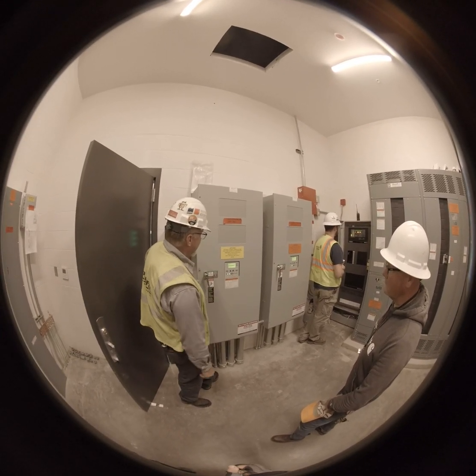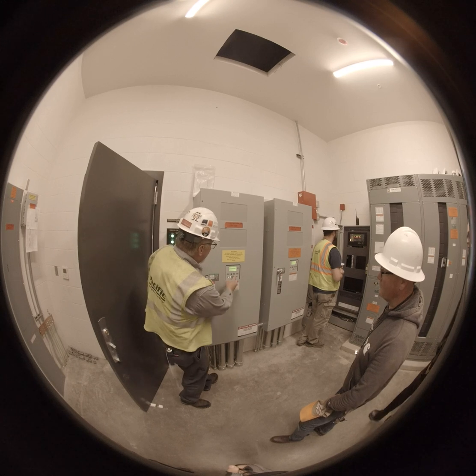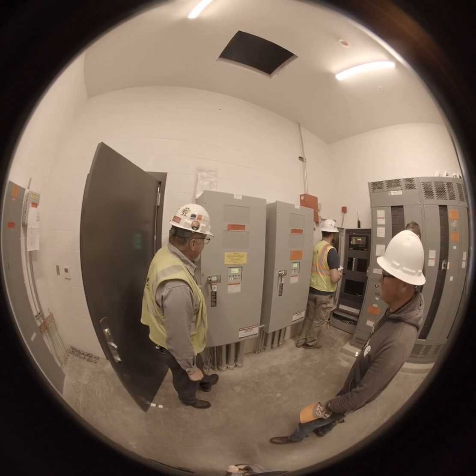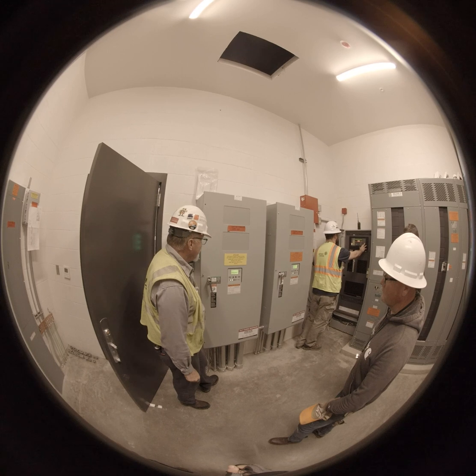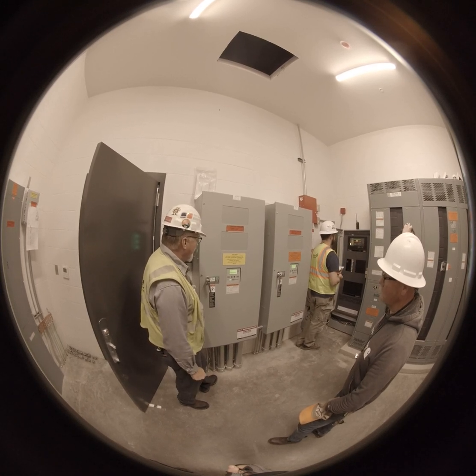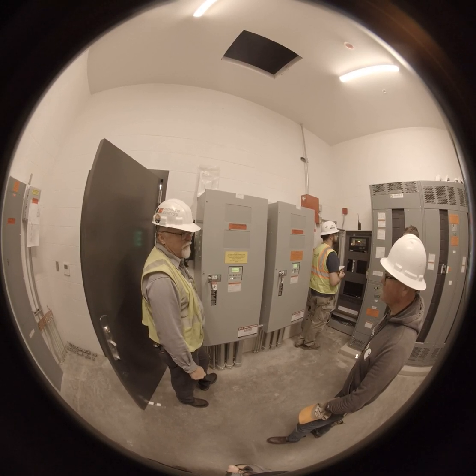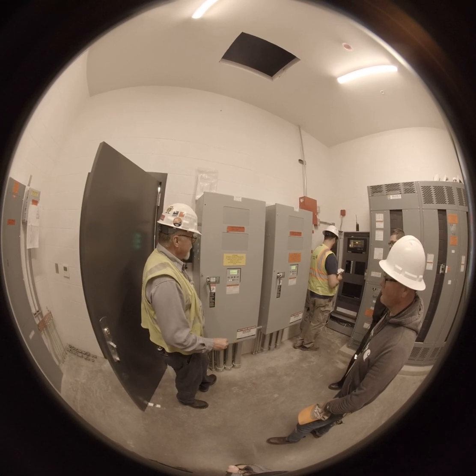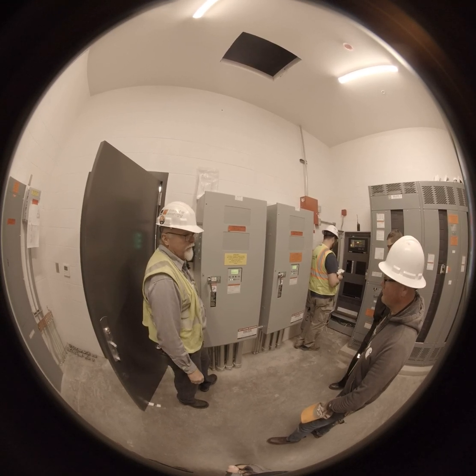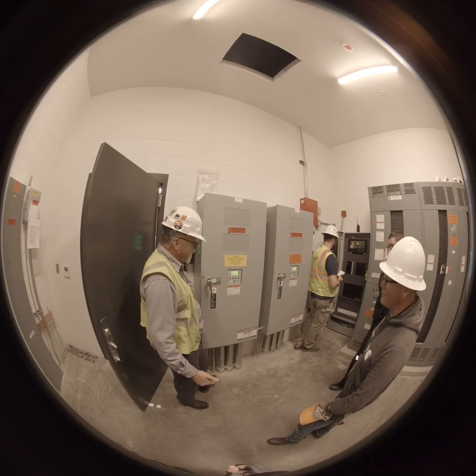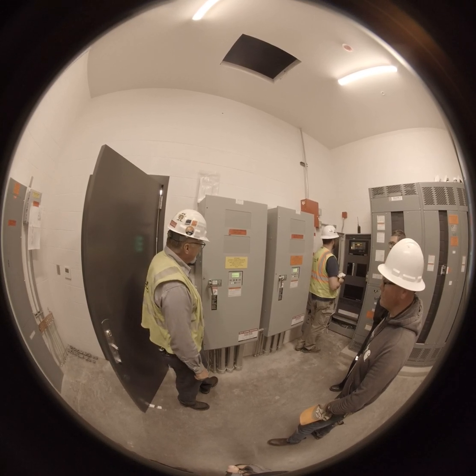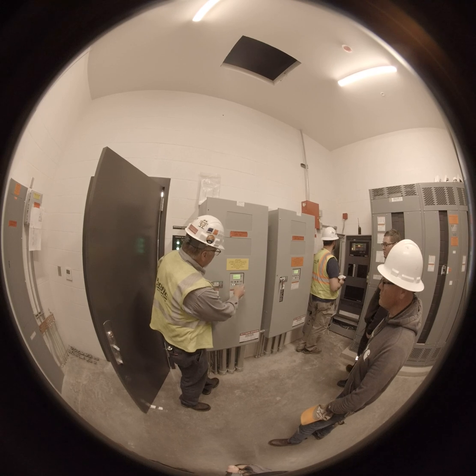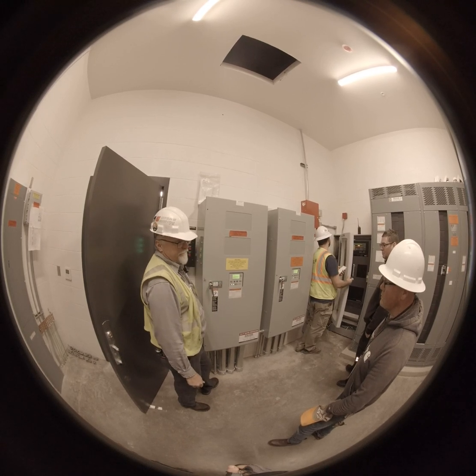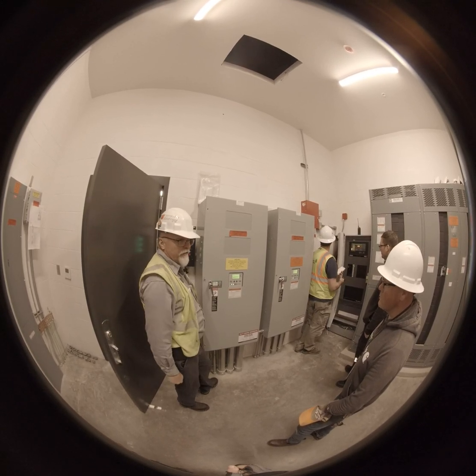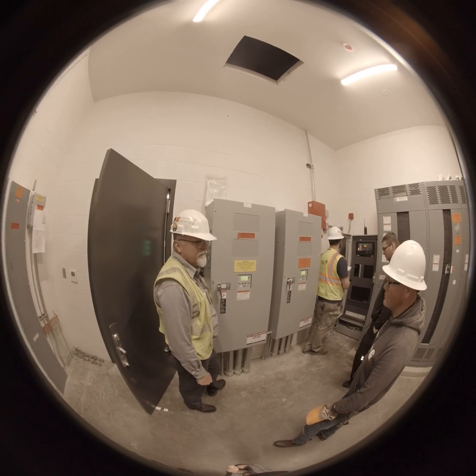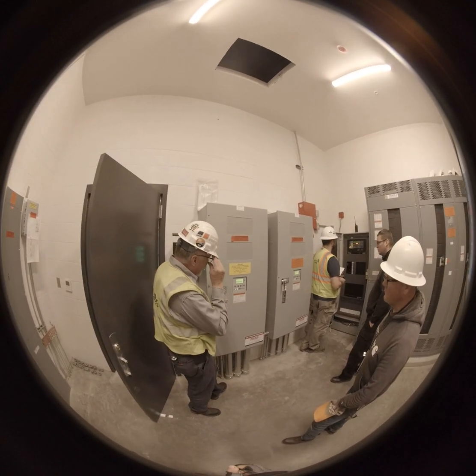We'll go down. No, actually one more. Okay, time delay from normal to emergency on a utility failure is 0 seconds, because we want to get that thing going quick. The engine's going to be warm out there and everything. We want to get her going, so we've got it at 0 seconds. Now, in the test mode, if you flip the test switch over here, we're still going to leave it at 0 seconds. No reason not to.